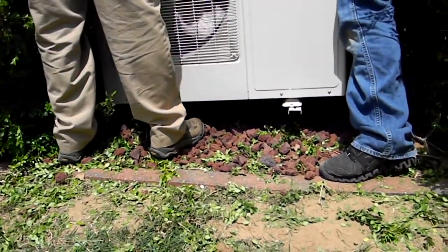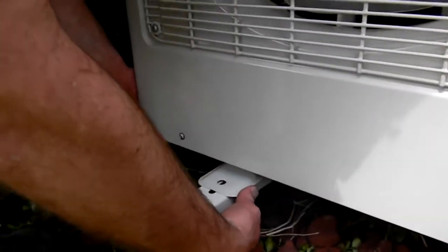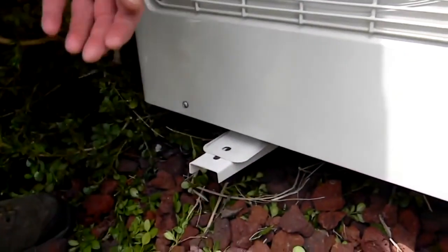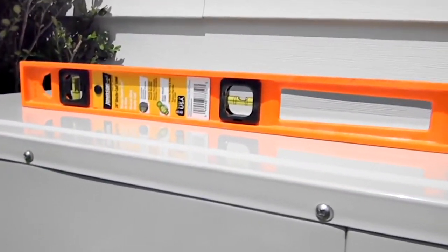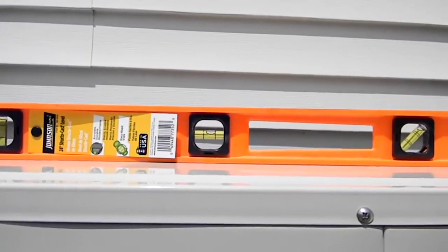After securing the brackets, place the unit on the brackets. Check and make sure that the unit is setting level. Next, fasten the unit to the brackets using 5/16 or 3/8 inch bolts and nuts. Check the level one more time before proceeding.